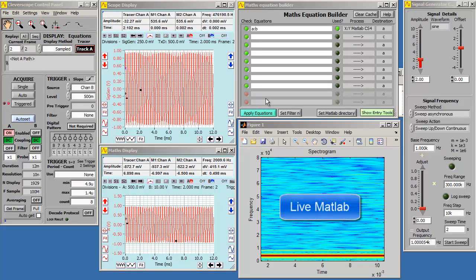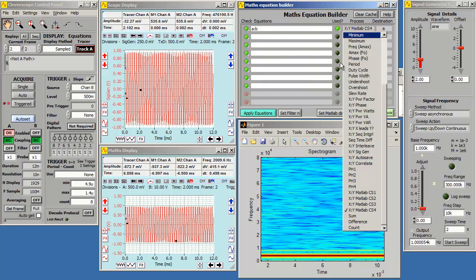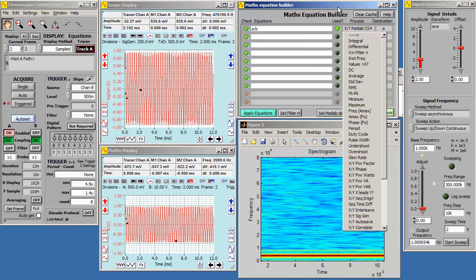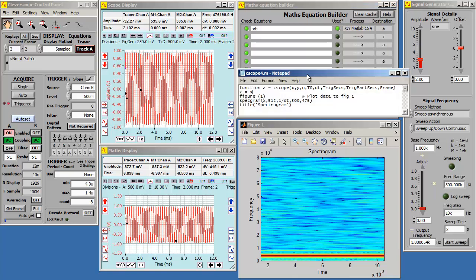Cleverscope includes a live MATLAB interface via Maths. We do this using four gateway M functions entered into the Maths Equation Builder. Here we are calling one of these functions. You can see the four of them, labeled CS1-4. Each gateway function operates using a MATLAB M file, which is just text that is run by MATLAB. In this case, we are using cscope4.m.